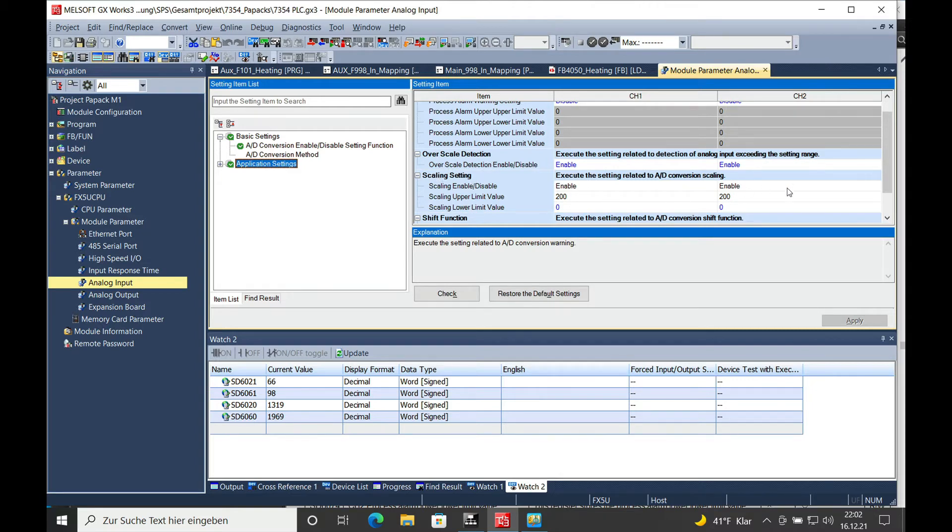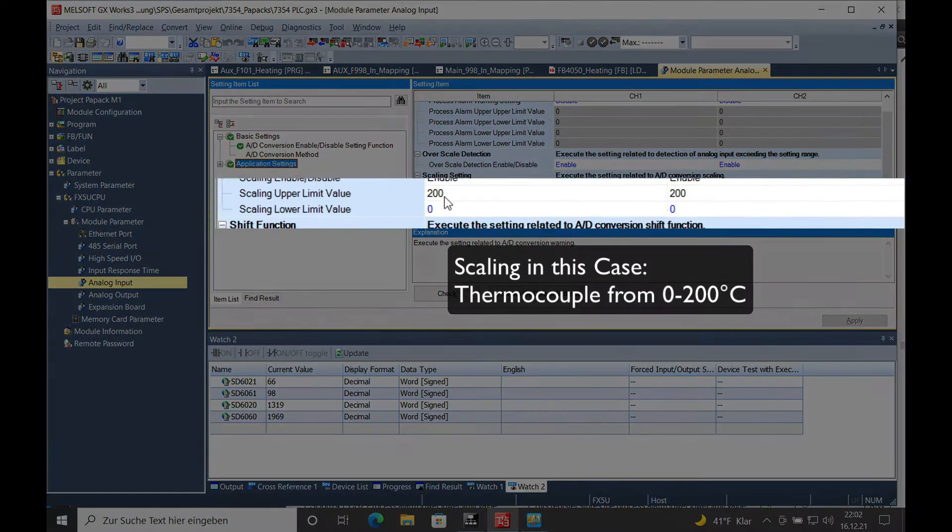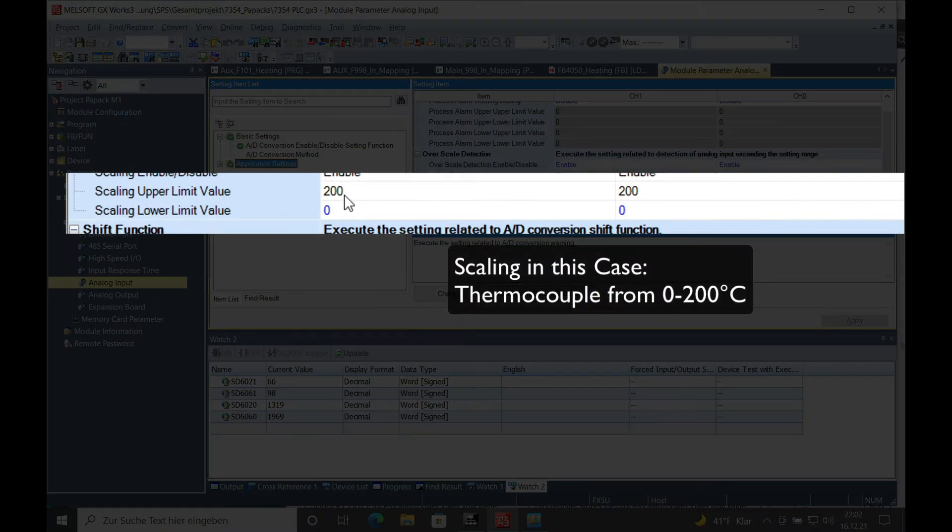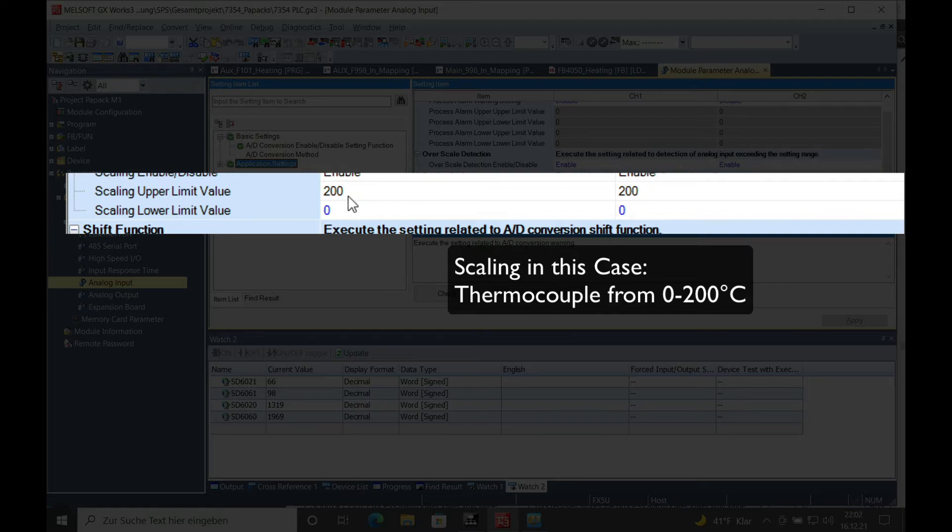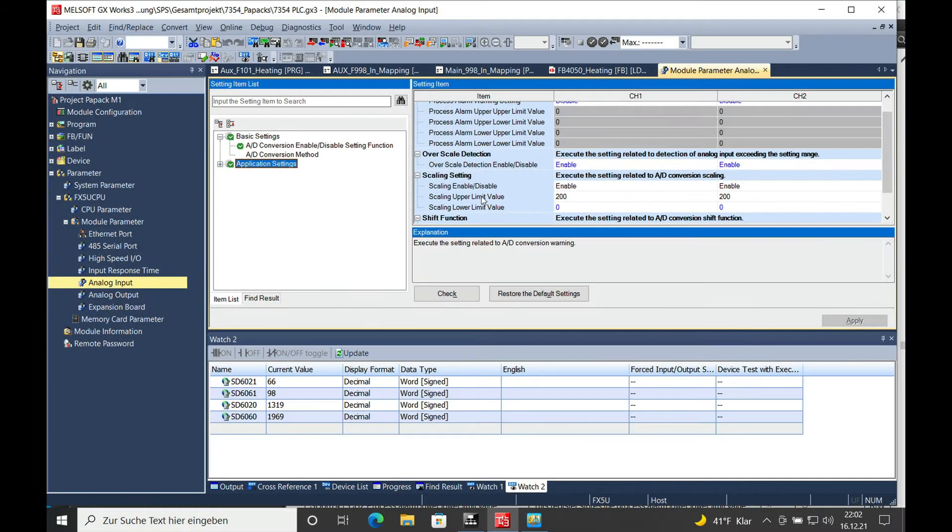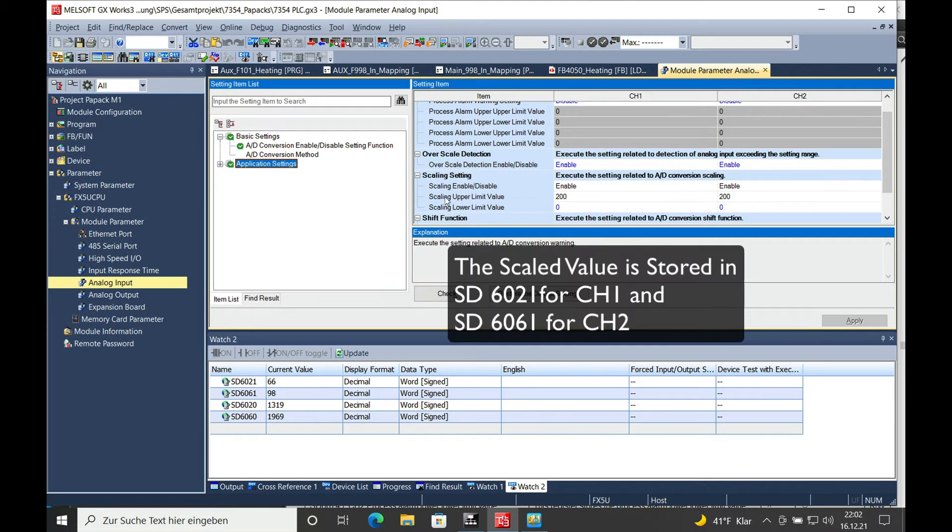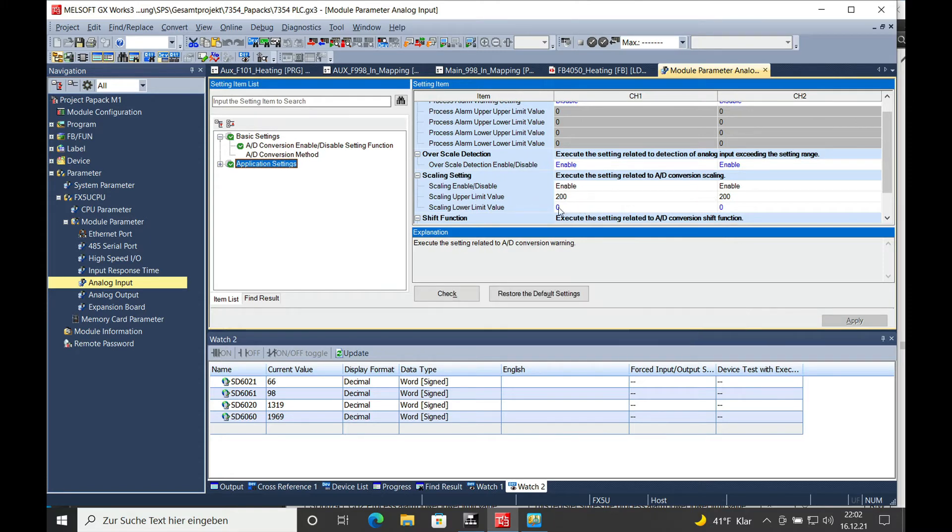For example, I got a thermal couple which detects a temperature from 0 to 200 degrees. So I set both upper scaling values to 200 and the lower scaling value to 0, because the thermal couple is from 0 to 200 centigrade.